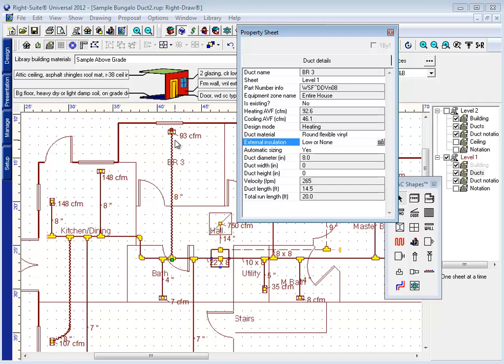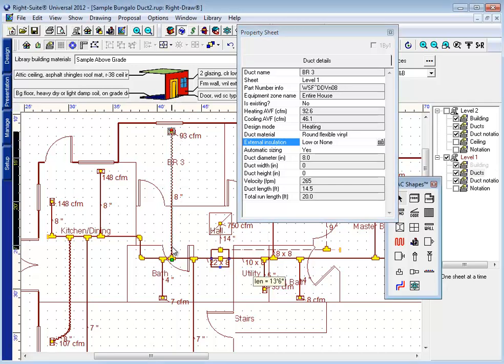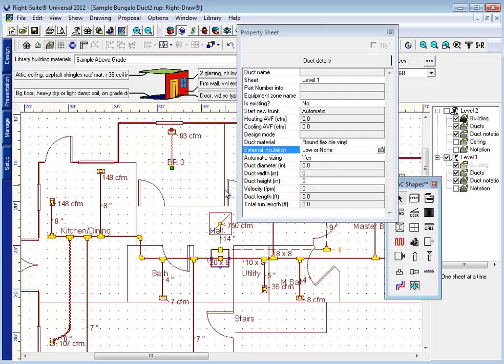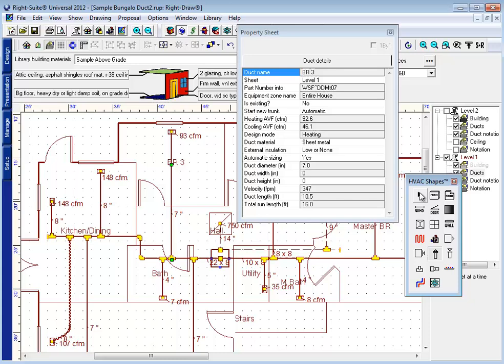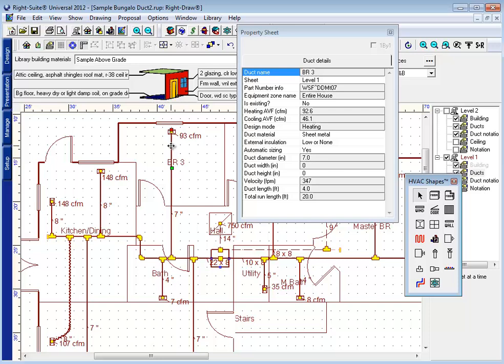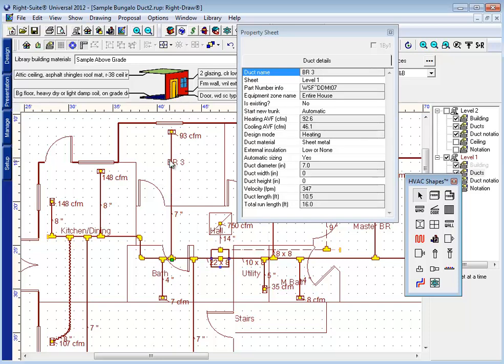Now, if you do want to show this for purposes of inspection or installation or because you are using the materials list, then you would want to draw this duct as two pieces. Draw the first piece to the length that you want and then finish the connection. This duct is going to size as one continuous piece of duct initially, but it is considered two separate pieces of duct. Technically speaking, this duct here, as it connects at both ends to another duct, is considered a trunk line.